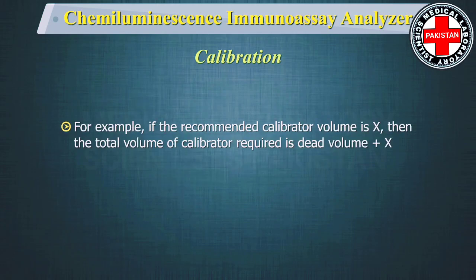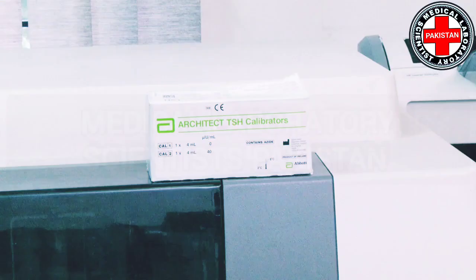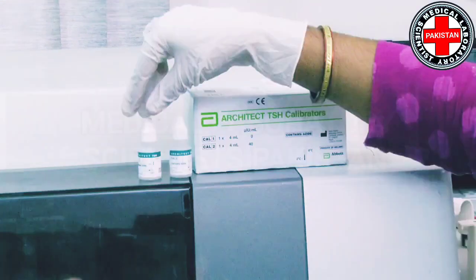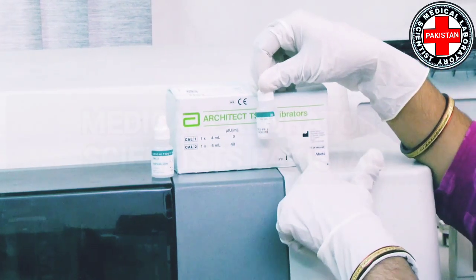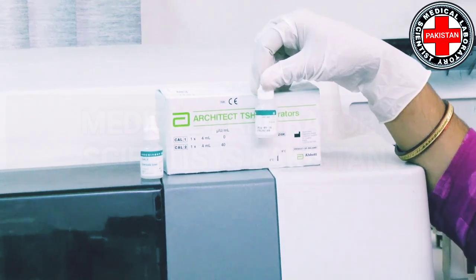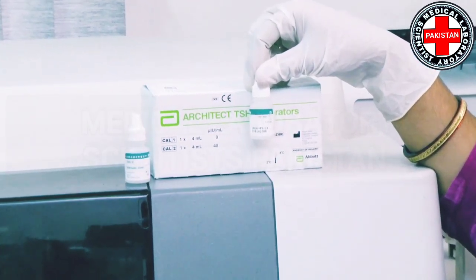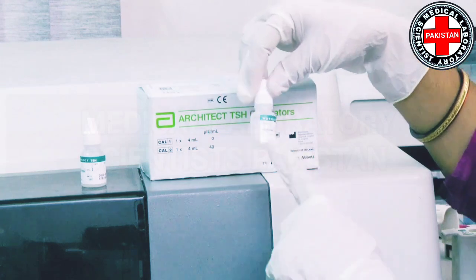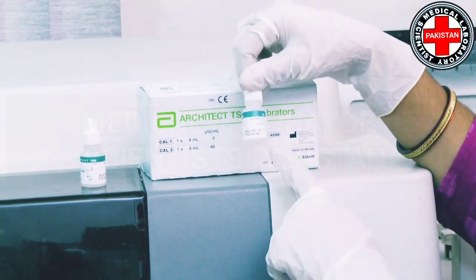For example, if the recommended calibrator volume is X, then the total volume of calibrator required is dead volume plus X. For TSH, two calibrators are used. The calibrators yield concentrations as shown on the kit insert. TSH calibrator stability is 29 days, which means every 29 days the assay has to be recalibrated.